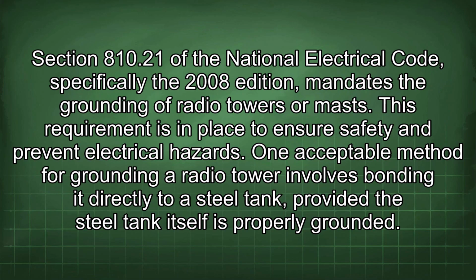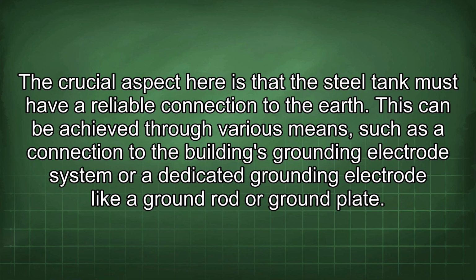Section 810.21 of the National Electrical Code, specifically the 2008 edition, mandates the grounding of radio towers or masts. This requirement is in place to ensure safety and prevent electrical hazards. One acceptable method for grounding a radio tower involves bonding it directly to a steel tank, provided the steel tank itself is properly grounded. The crucial aspect here is that the steel tank must have a reliable connection to the earth. This can be achieved through various means, such as a connection to the building's grounding electrode system or a dedicated grounding electrode like a ground rod or ground plate.